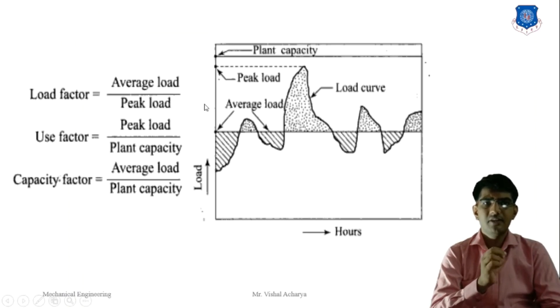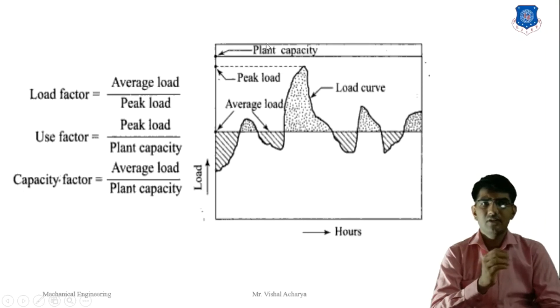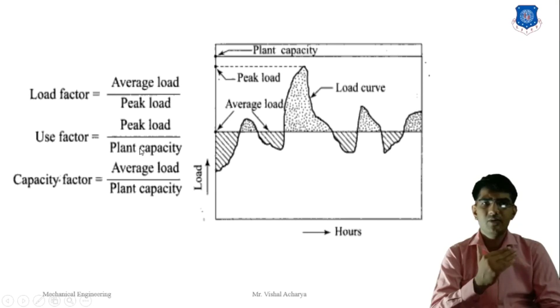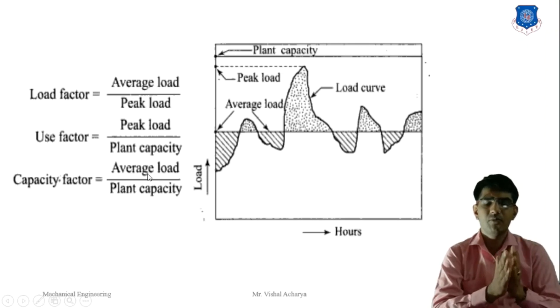The graph represents the year's average load, showing peak load and plant capacity. From this: load factor = average load / peak load; use factor = peak load / plant capacity; and capacity factor = average load / plant capacity.